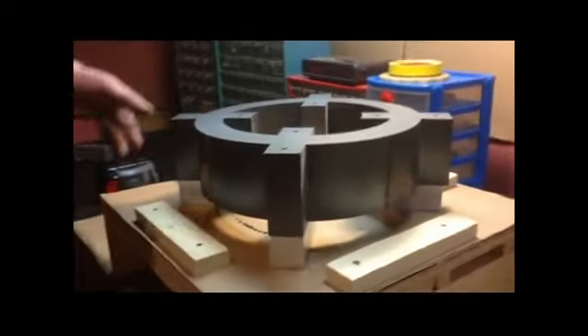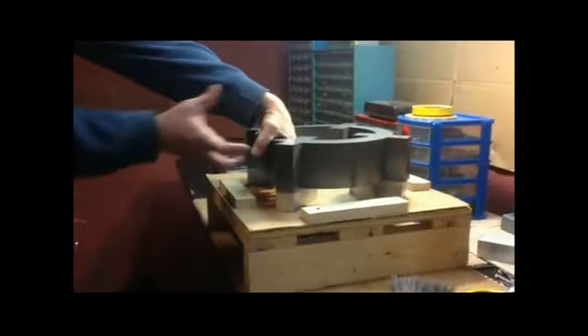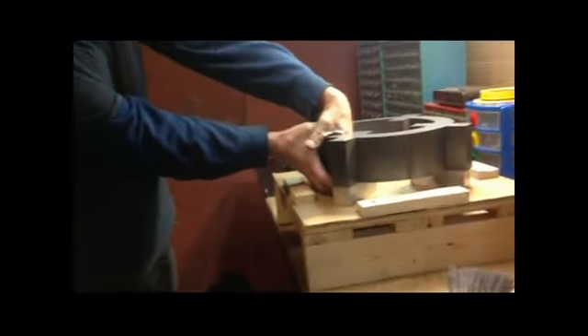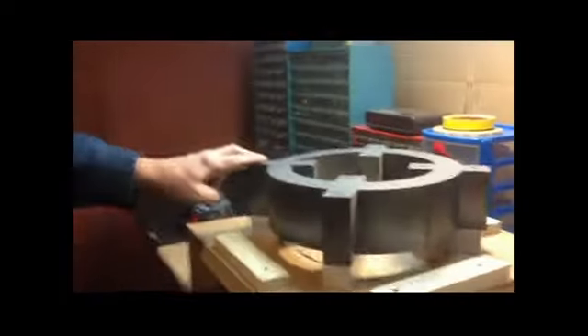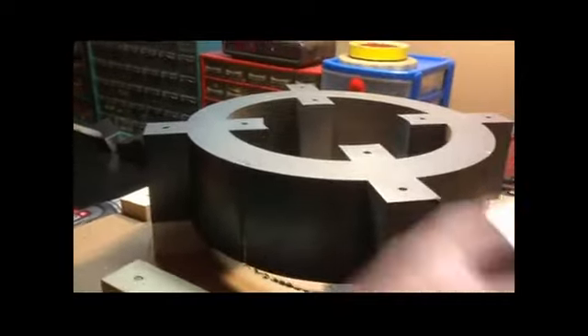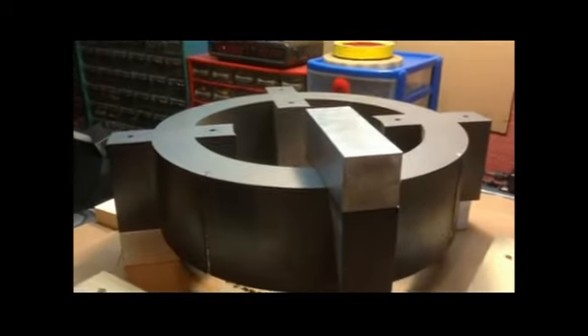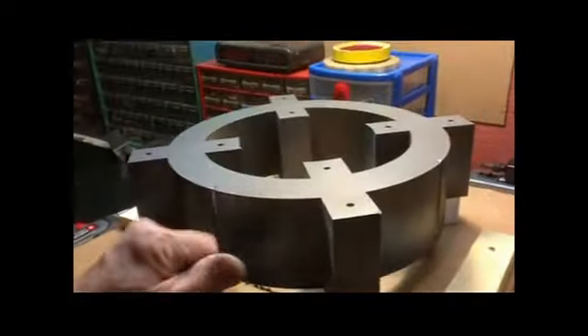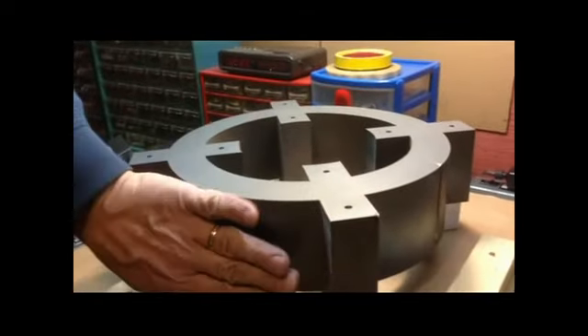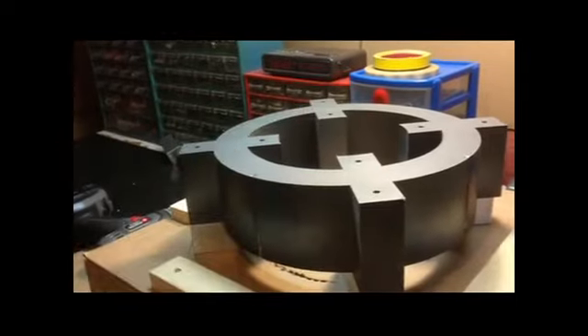What are these? These are the aluminum spacer blocks. They go on each side of the core, on the 4 legs, to give room for the winding area. You have to think of it as a 3-dimensional winding area, where you need space for the wire in between the rectangles. So you have to have the spacers in there to provide the space for the wire, because you can't put the end plates right up against it, and you can't bring the wire around since it would get bigger this way and that way. So you have to have the spacers.